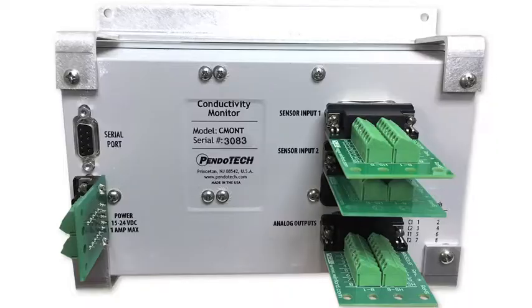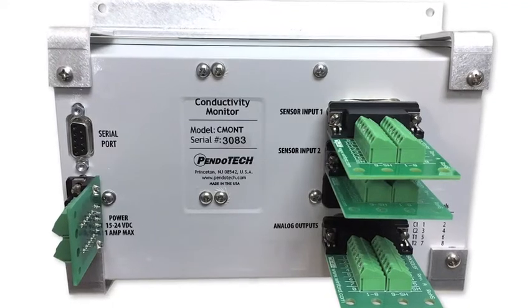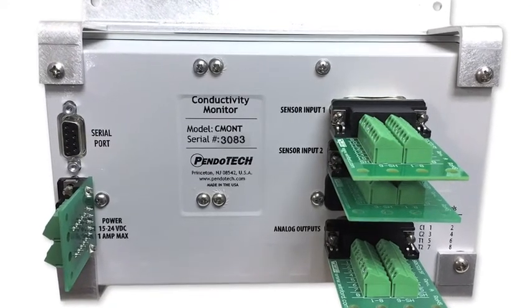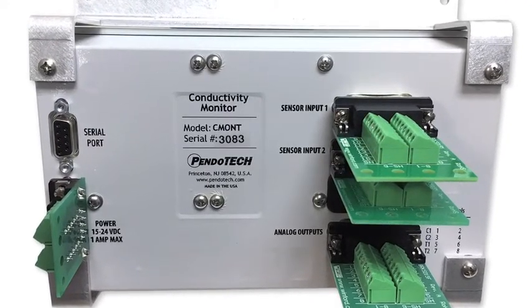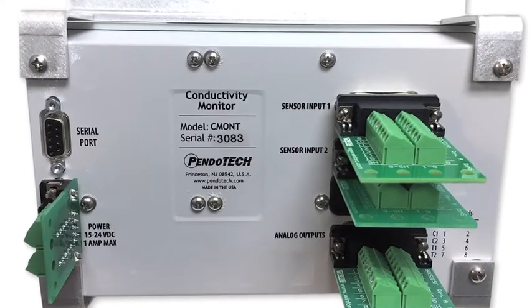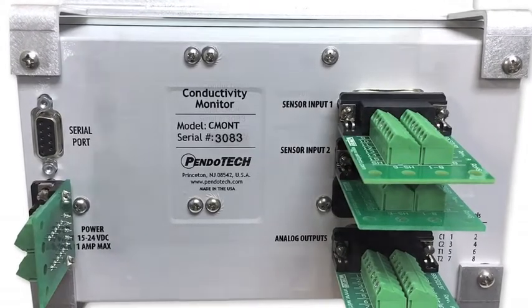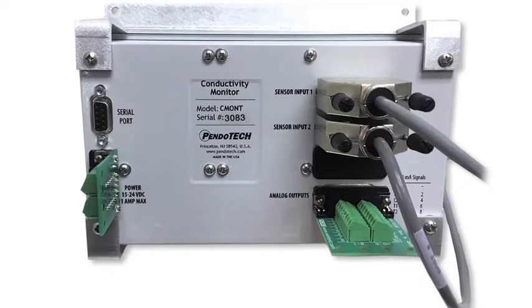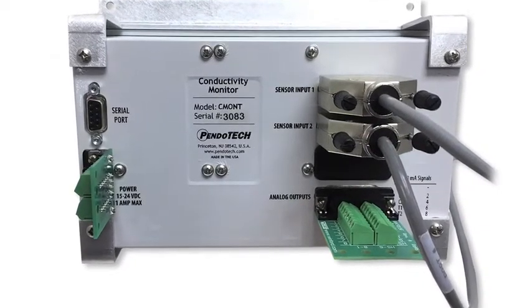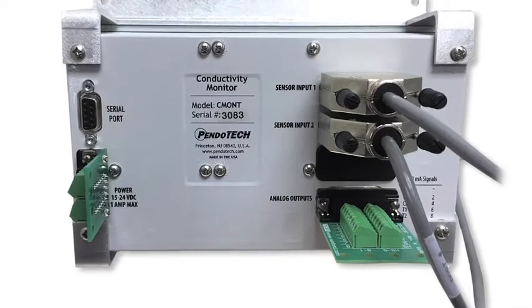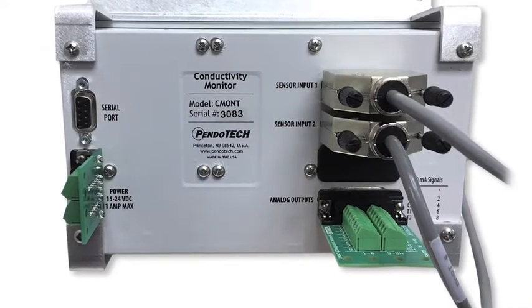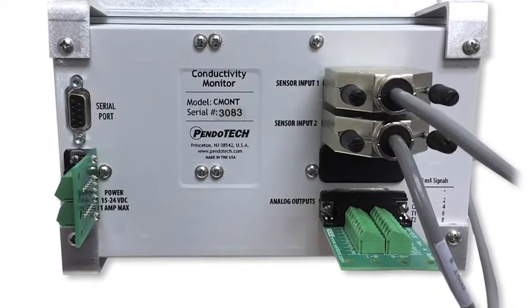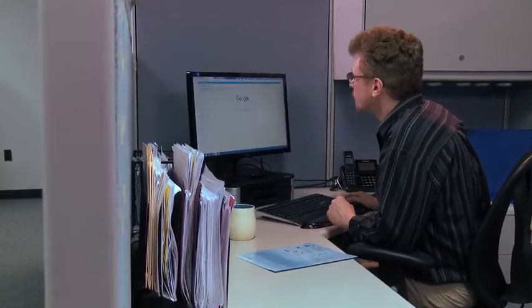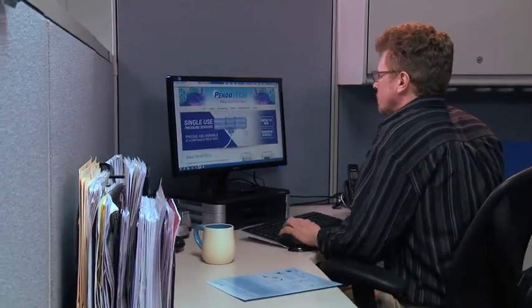For DIN rail mounting within an industrial cabinet where the design prefers to not have the unit exposed, the panel mount screw holes on the back are used to secure the bracket to the unit. In the kit are included screw terminal connectors for the inputs and outputs. This kit streamlines this type of installation. There is a technical note on the PendoTECH website with the required details for integrators to complete this type of installation. PendoTECH customers can search our website for the sensor that meets their needs.